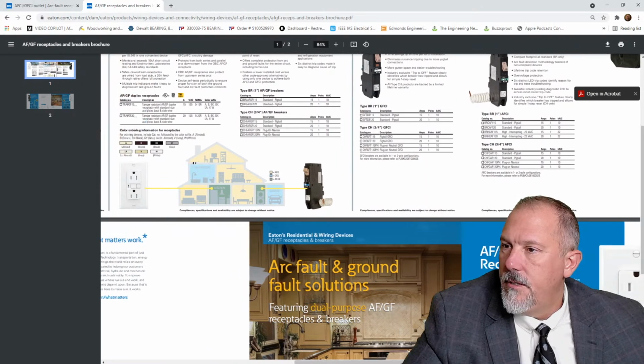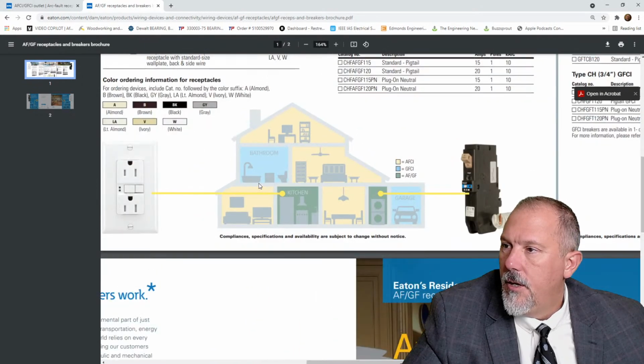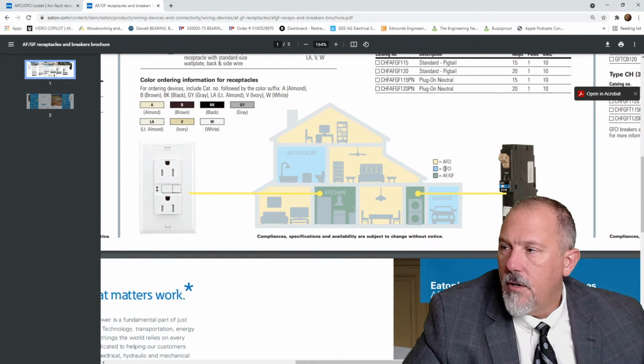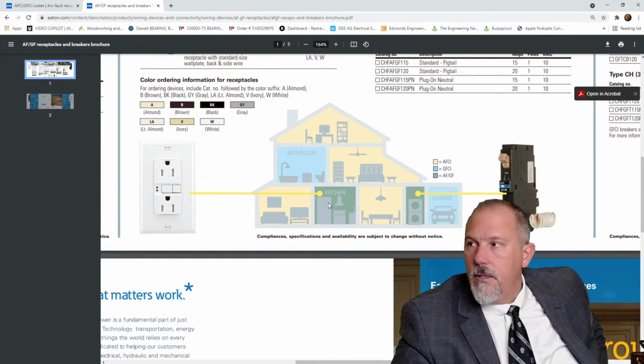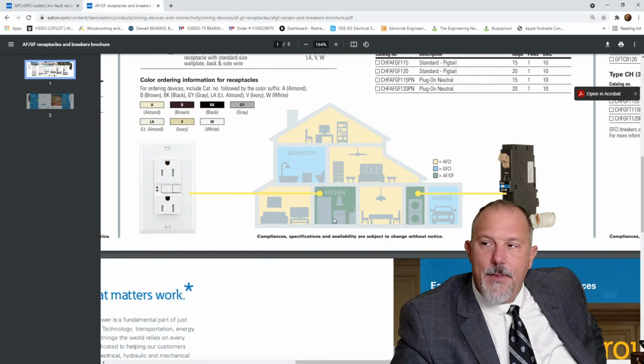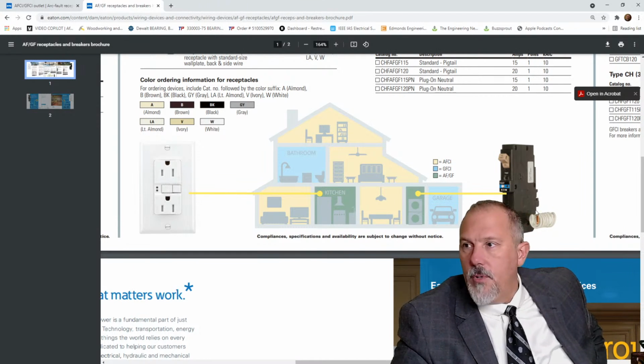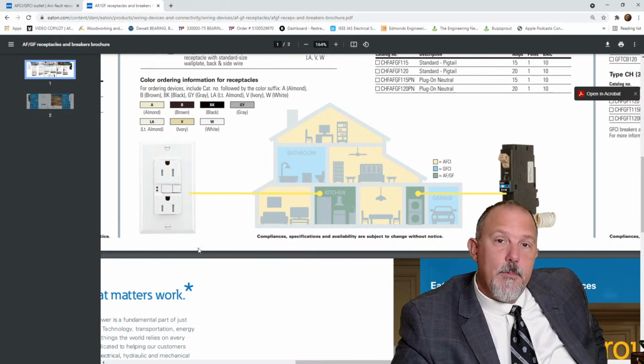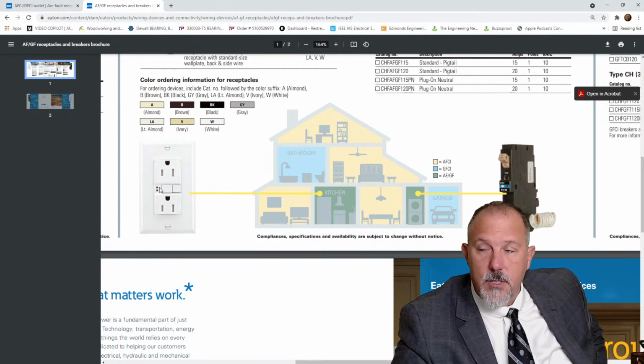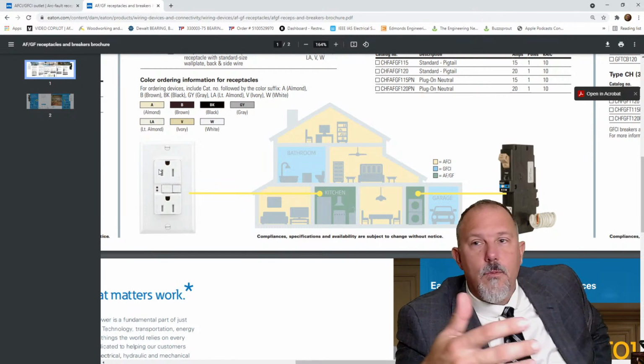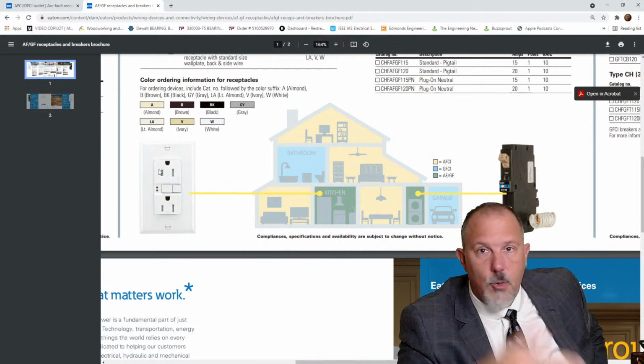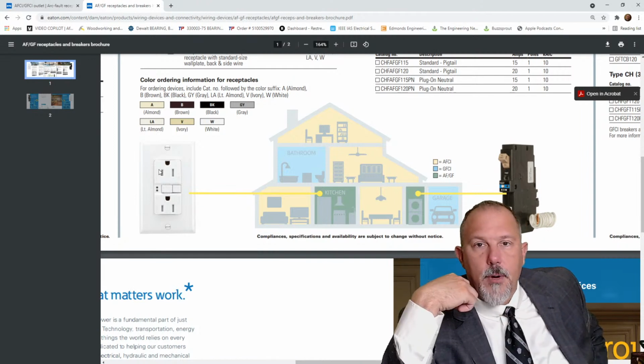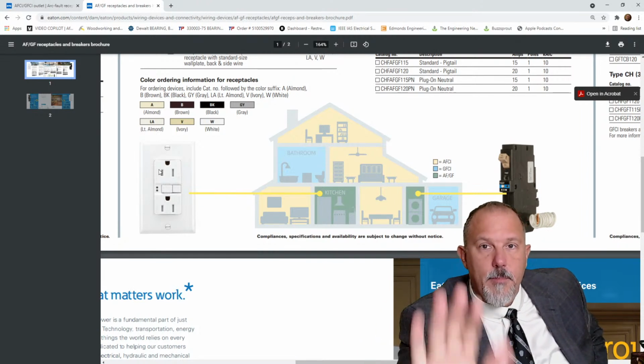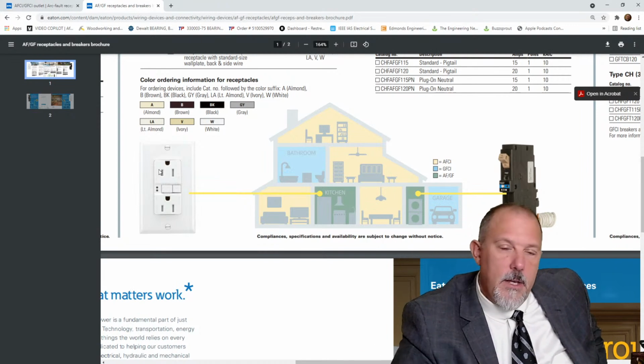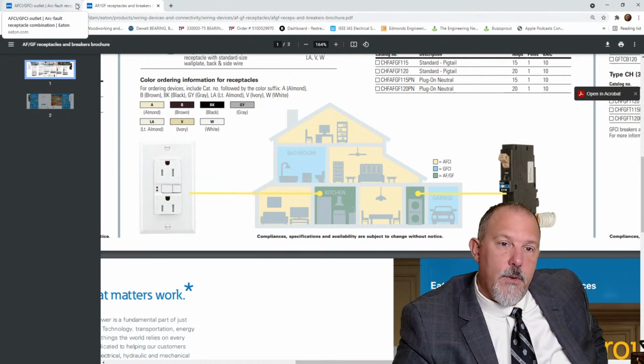So you could put an arc fault, ground fault to cover the laundry area and the kitchen. You could put it in a receptacle. You can put it in a breaker. And I'll tell you, we make these blank face receptacle or wiring device type solutions that you can feed. If you want to put it on the refrigerator, for example, and you don't want any other loads and you can't put the breaker in, you can put a receptacle in that's a blank face feeding another receptacle, and it'll give you both arc fault and ground fault protection.